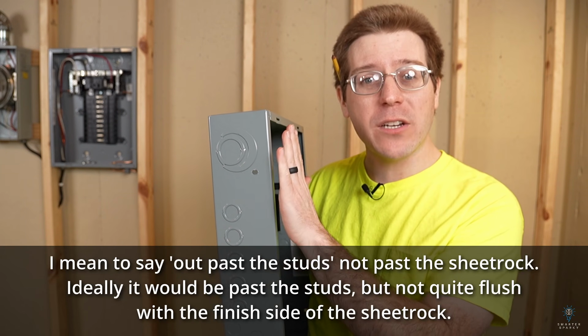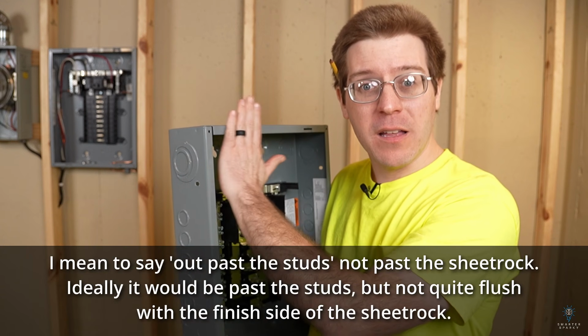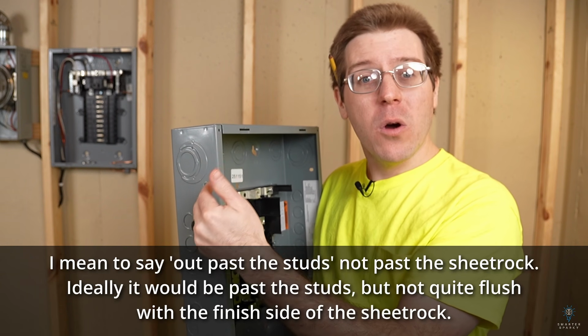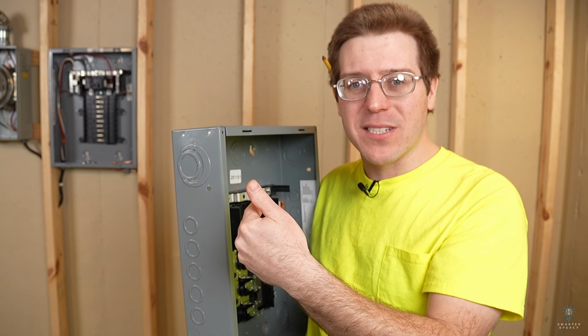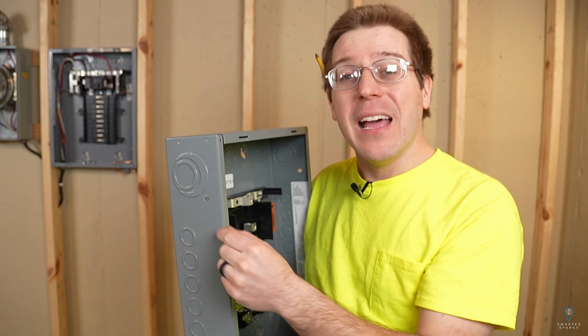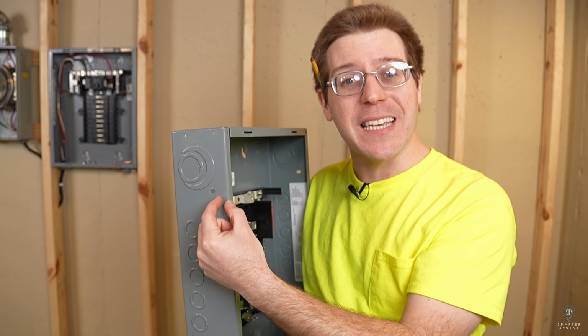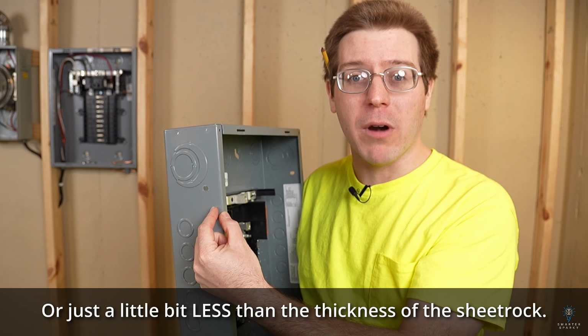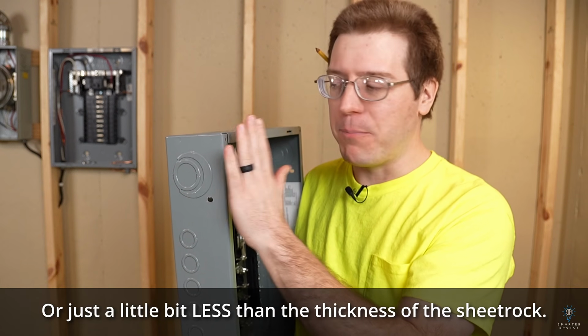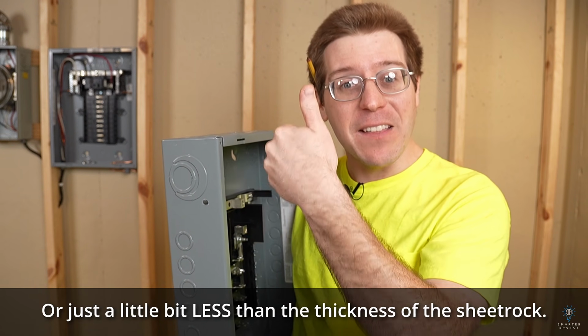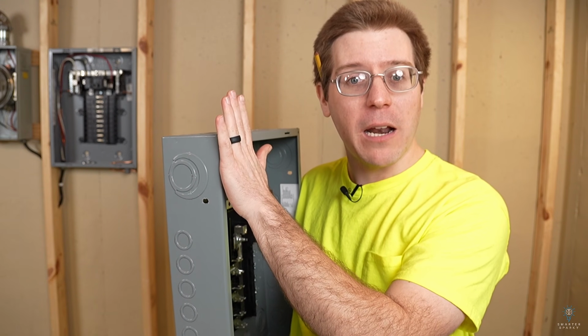So we don't actually want the face of the panel flush with the studs. We actually want it poking out of the studs just a little bit. As a matter of fact, we're gonna want it sticking out the thickness of our sheetrock. We don't want sheetrock between the panel face and the cover. We want metal to metal on the cover.